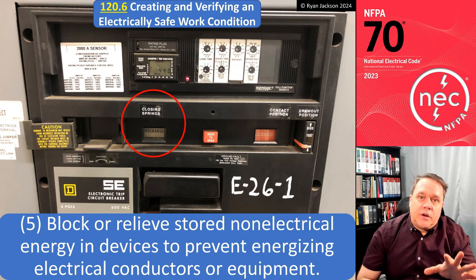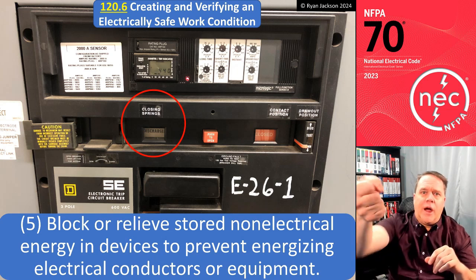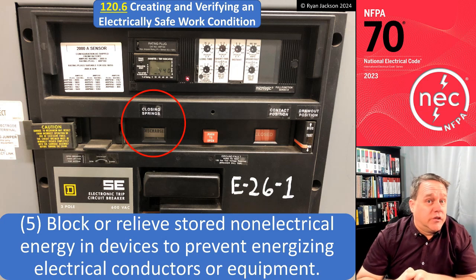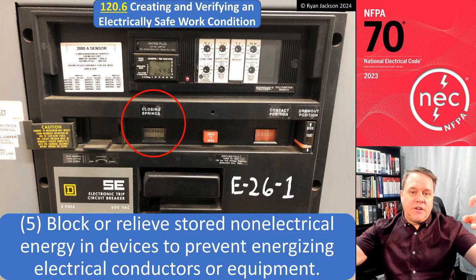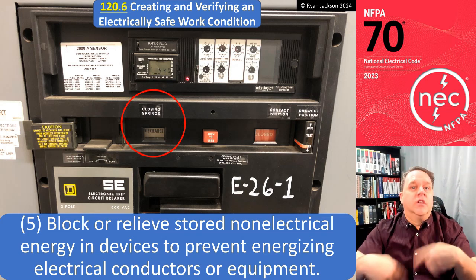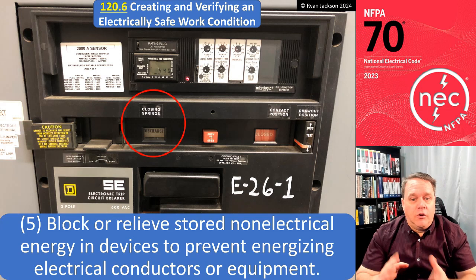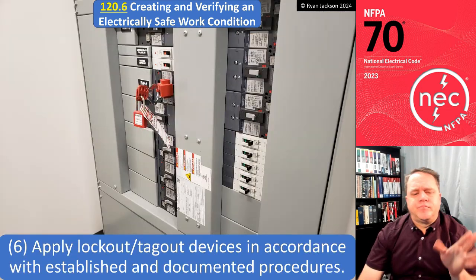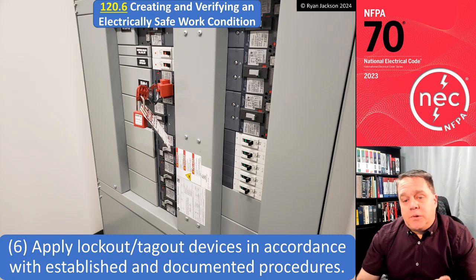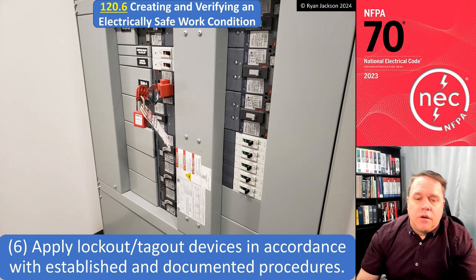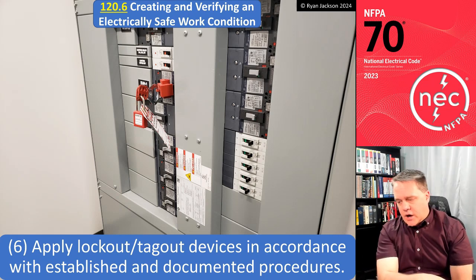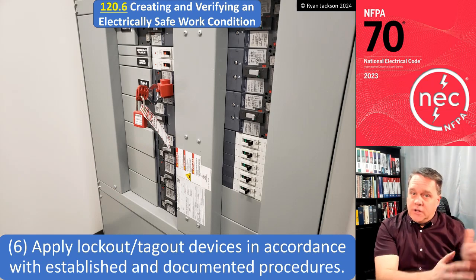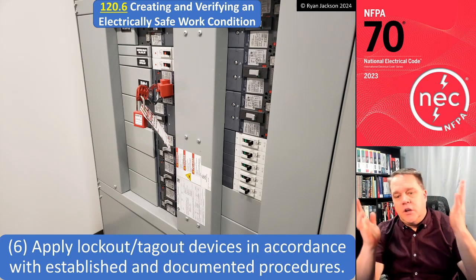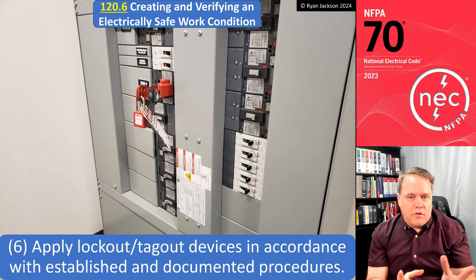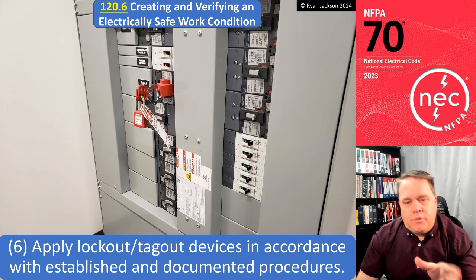On a circuit breaker where you have to prime the handle, what are you doing? You're putting tension on the spring. When that spring is under tension, we need to relieve that tension so that it doesn't automatically energize. Item 6, apply lockout tagout devices in accordance with established and documented procedures. So figure out what to shut off, shut it off, relieve any electrical energy, relieve any non-electrical energy, put your lock on it or your tagout device in accordance with established documented procedures.